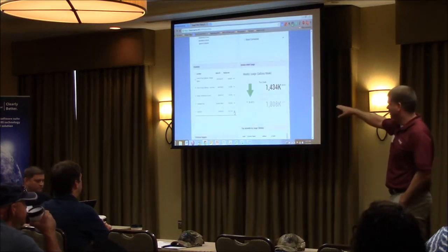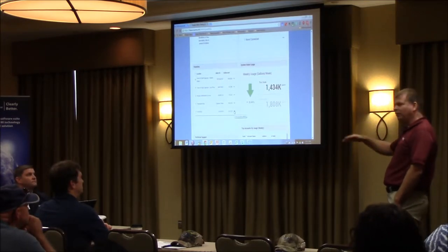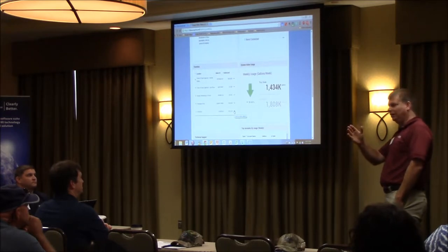We can, just like Jeff just showed, see their baseline is 30 gallons an hour. If we let them know when we come in on Monday morning that they've had a leak all weekend, they need to get that fixed.